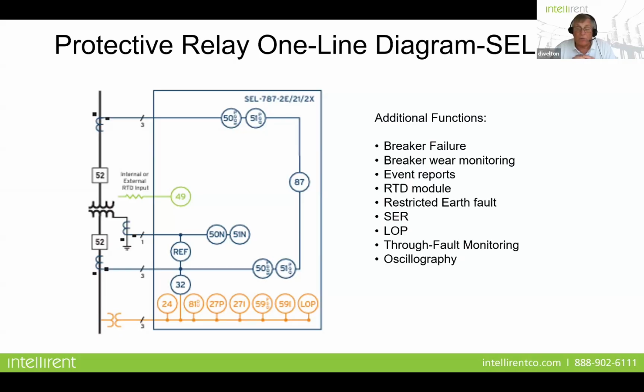So he got in his car and drove out the next morning to the site, and by the time he got there, they had already started to disconnect the main connections to the transformer. They were putting up scaffolding. They had all their test equipment out, and he walked up to the foreman and said, by the way, before you start doing anything, have you looked at the relay and checked the oscillography and the event recorder? And he was kind of dismissive. He said, yeah, no, go away, young fellow. We've got to find out what's wrong with this transformer.